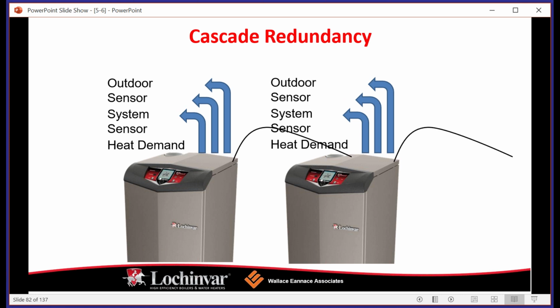So why do we need more than one boiler? Well, because a couple of reasons. The first and foremost is redundancy. Okay, if you're in an application, basically anything outside of residential, you're going to want to have the ability to have 2 boilers that are able to handle the load. So let's say you had, for whatever reason, catastrophic failure on one of the pieces of equipment, you don't lose the whole building, right? You still have the ability for the other boiler to kind of limp along and carry that load until the other boiler is repaired. Also, again, for efficiency purposes, you're going to want to run these boilers together. So, you know, believe it or not, you're going to have some people who will argue with you about it.